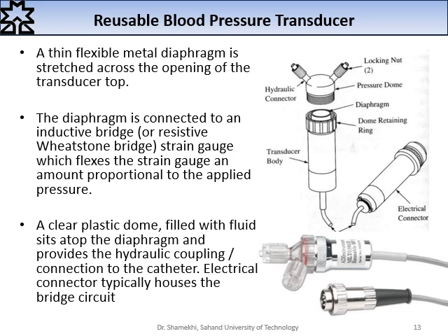The extravascular pressure sensor consists of two main parts. The first one is the reusable part. As you can see, this part is the reusable part of the sensor, and this part is another connected catheter and piping parts, some parts of a sensor which we should exchange per recording.